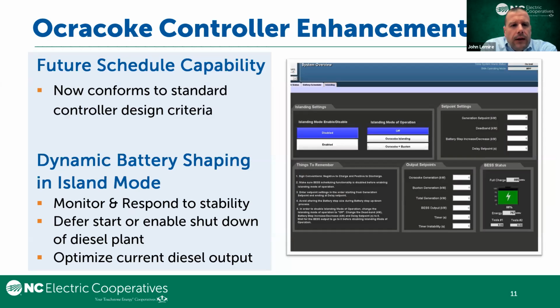The third one is to be flexible and adapt. A couple years after the Ocracoke microgrid came online, in response to running the system in an island for maintenance or during an outage, our engineering team came and said it would be really nice to have a way that you could dynamically use the battery to shape and operate. So what we were doing is we were bringing the diesel online. We would then bring the battery online and base load the output, use the diesel to regulate, and then adjust if we were doing a long run, charge back the battery.